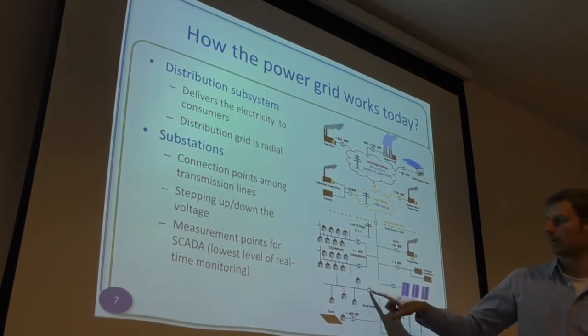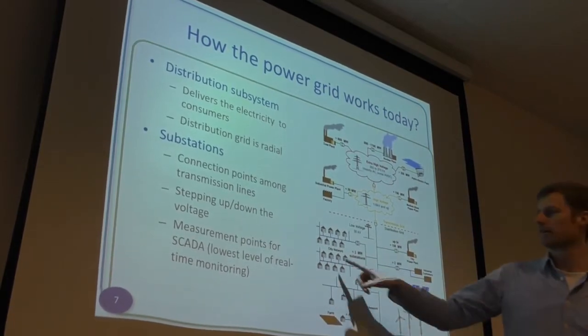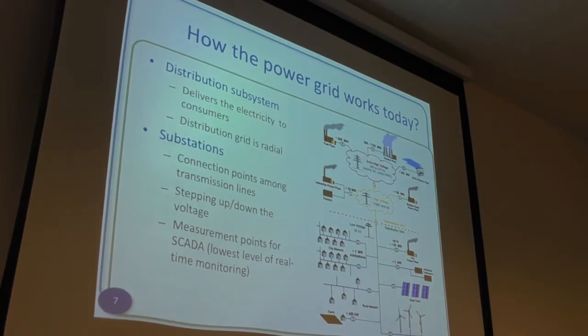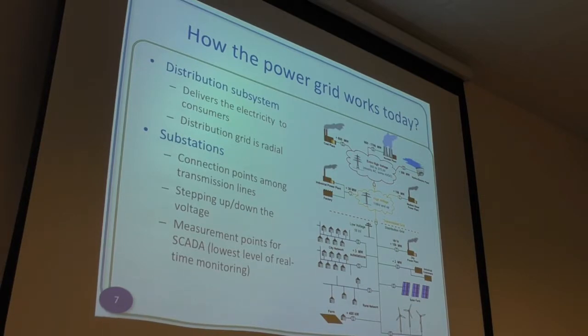SCADA is used to monitor performance metrics of the power network — typically a new measurement every four seconds. But the measurements are only at these substation points, meaning you don't have measurements from further into the network, so you don't actually know what's going on at the individual households. You can also send commands through SCADA. The main function of SCADA is collecting monitoring data and then taking action — there's a control center with someone monitoring and a decision-making step.